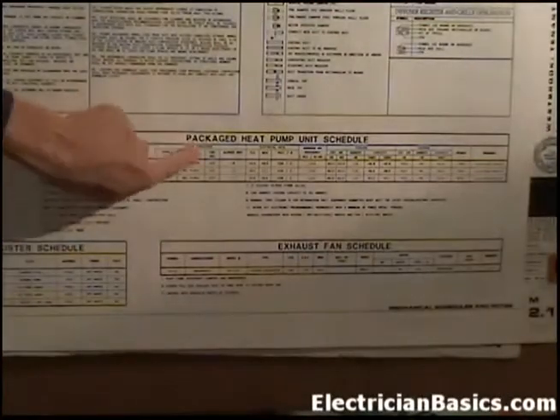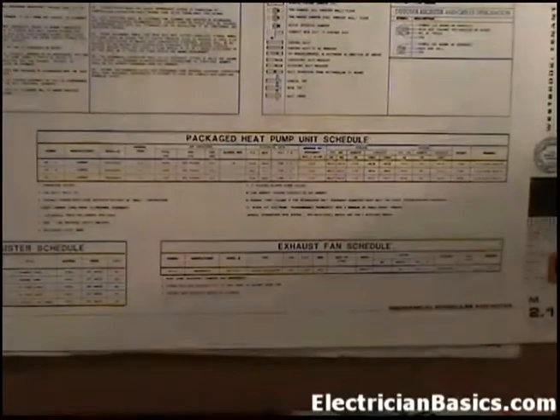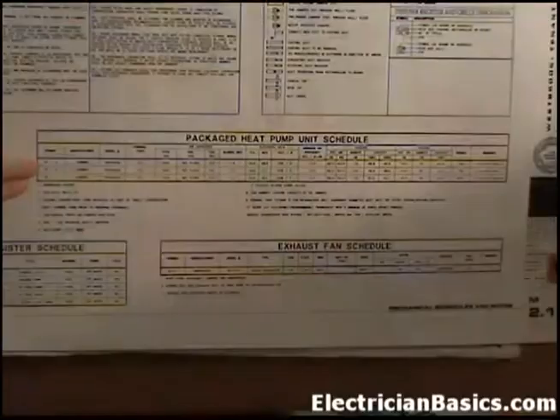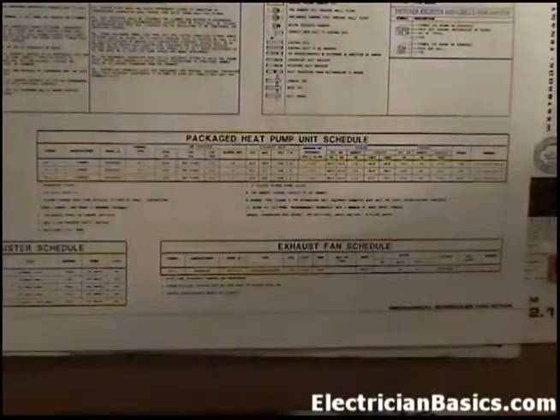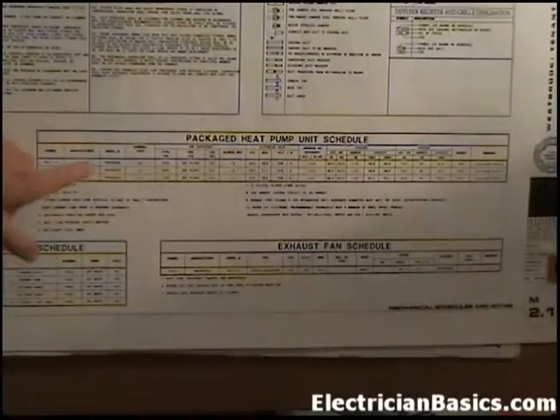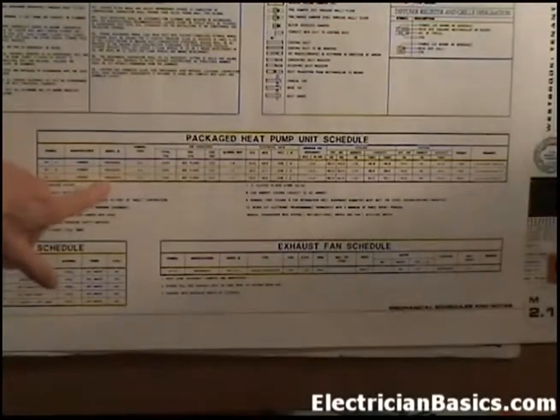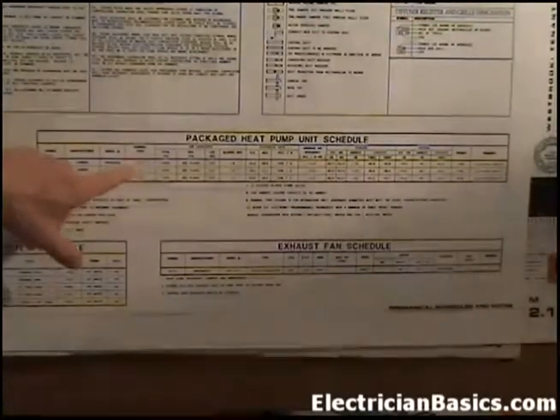Okay, so now we're looking at our packaged heat pumps unit schedule. These are the heat pumps that are going to be on the roof for the heating and air conditioning. Now we have three different types. If you look here, A, B, and C, those are the symbols given. And it gives the manufacturer, which is Carrier, and the model number. So there's three different model numbers because they're three different sizes. And you look at the size in tons: a 5-ton, a 4-ton, and a 3-ton.